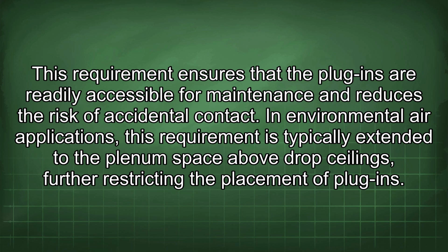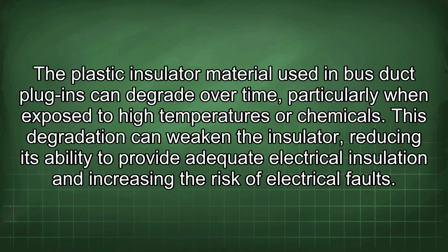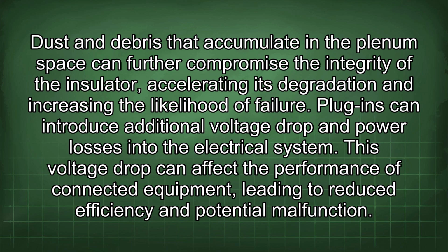The plastic insulator material used in bus duct plug-ins can degrade over time, particularly when exposed to high temperatures or chemicals. This degradation can weaken the insulator, reducing its ability to provide adequate electrical insulation and increasing the risk of electrical faults. Dust and debris that accumulate in the plenum space can further compromise the integrity of the insulator, accelerating its degradation and increasing the likelihood of failure.